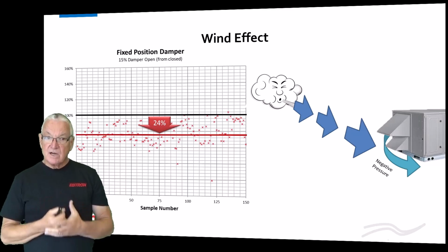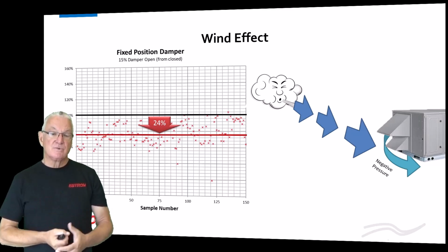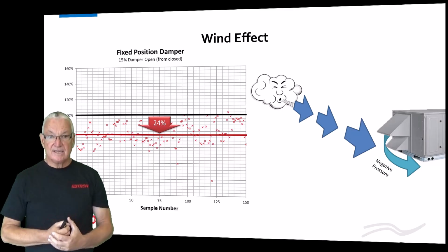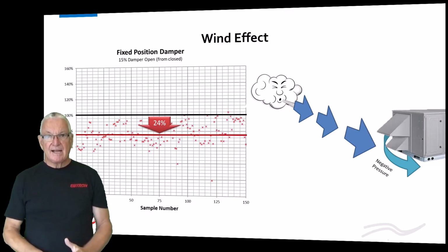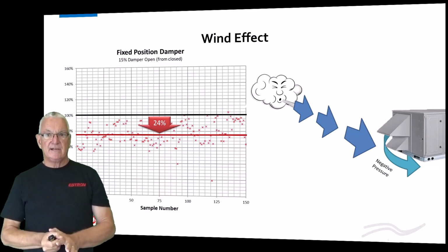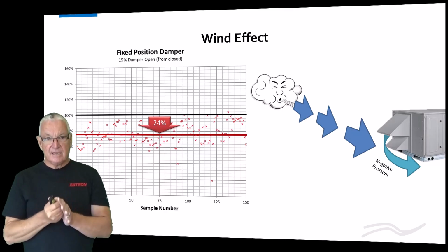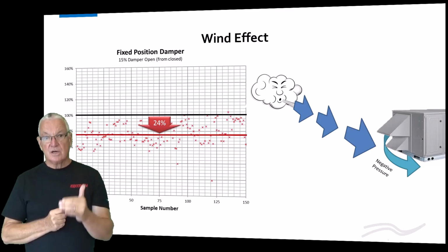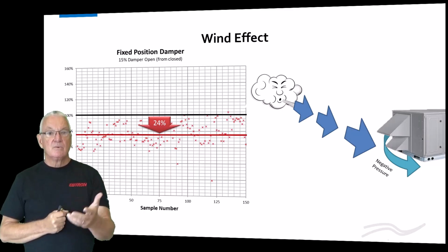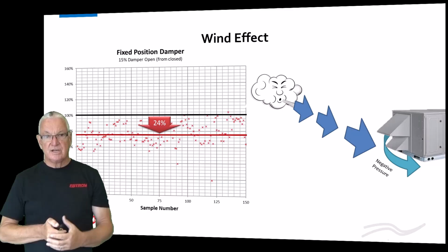Look at the running average of the result, which is really what that red solid line is, but control the actual input data, okay? It's another conversation. We're not going to have it today. We could have it, okay? But the big thing I want you to get from here is just going from no wind to a crosswind. We got this major change and reduction in outdoor airflow.